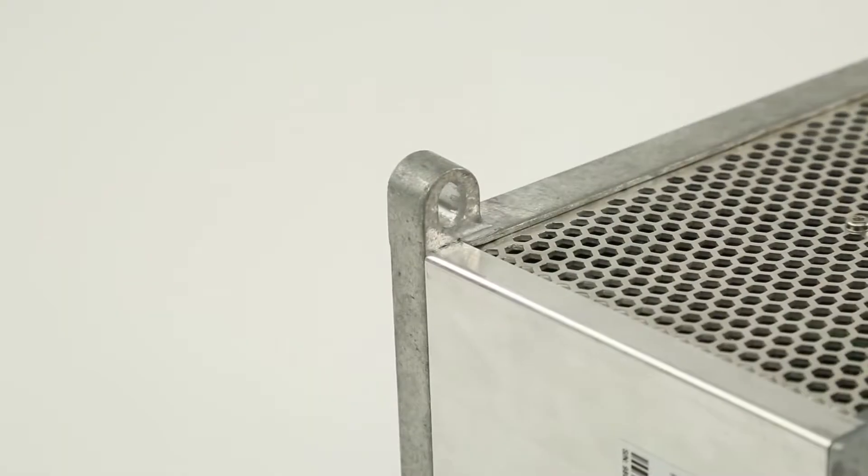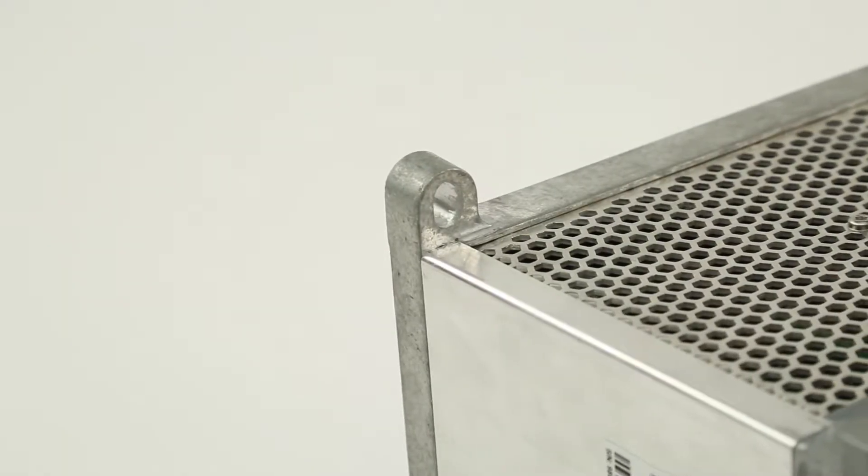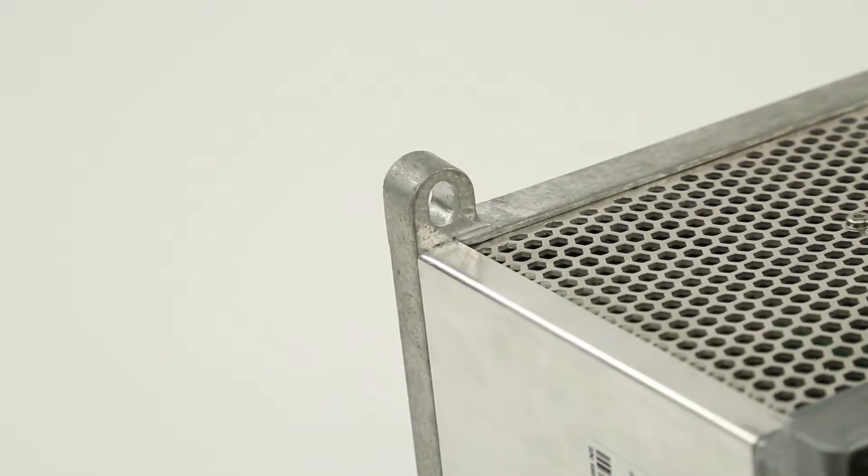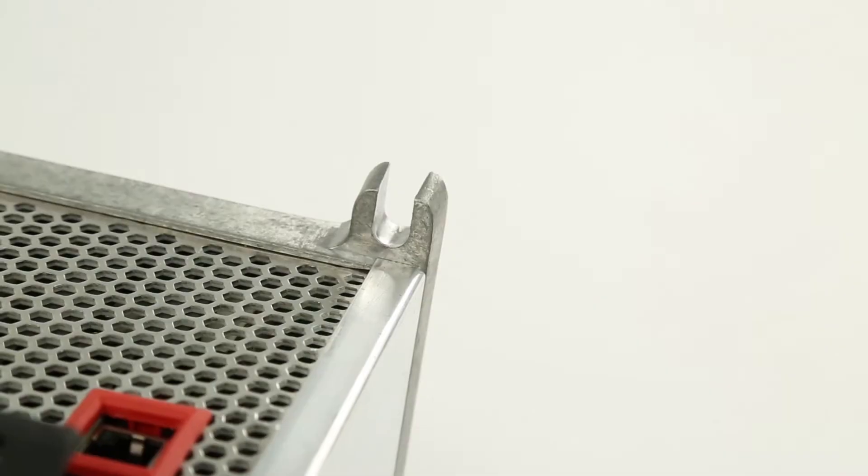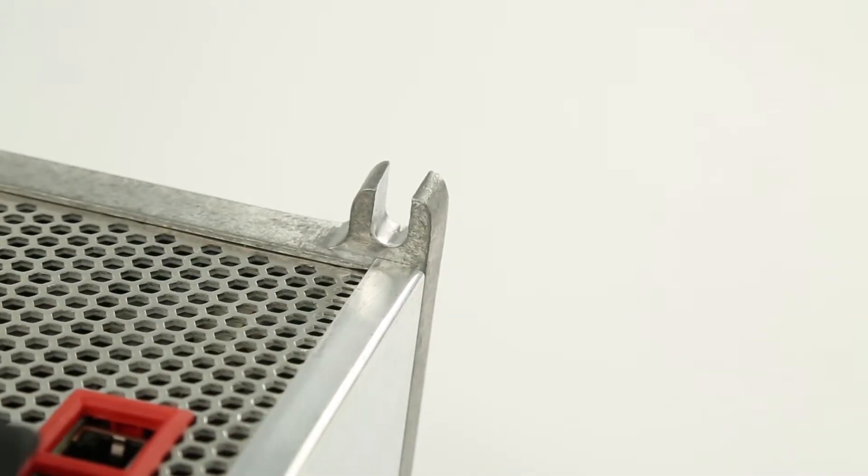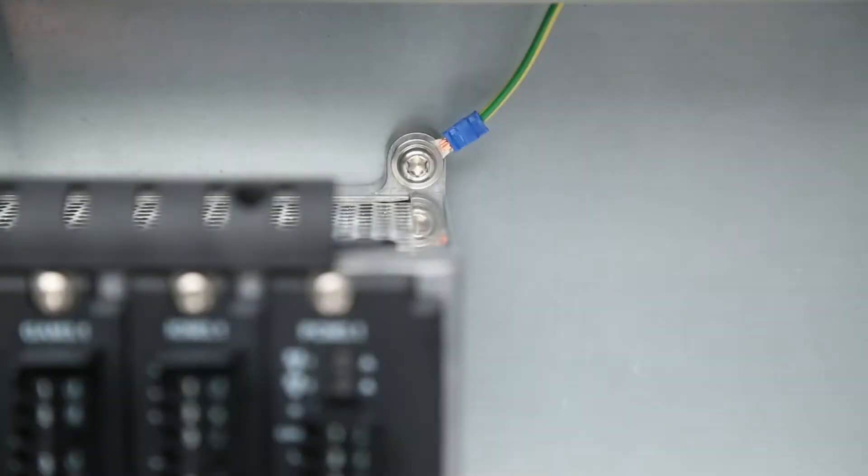When mounted, the rack frame must be grounded. The frame has four mounting brackets, two of which have position adjustment. A suitable ground connection must be made to one of the four brackets.